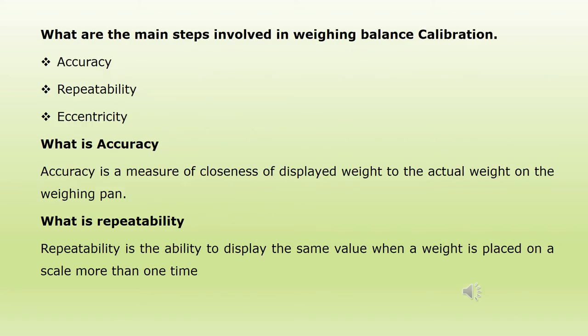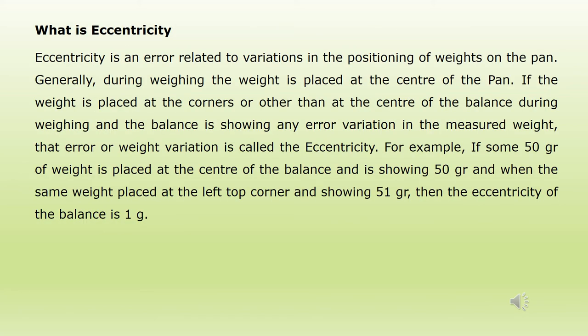What are the main steps involved in weighing balance calibration? The steps involved are verification of accuracy, repeatability, and eccentricity. What is accuracy? Accuracy is a measure of the closeness of the displayed weight to the actual weight on the weighing pan. What is repeatability? Repeatability is the ability to display the same value when a weight is placed on a scale more than one time. What is eccentricity? Eccentricity is an error related to variations in the positioning of weights on the pan.